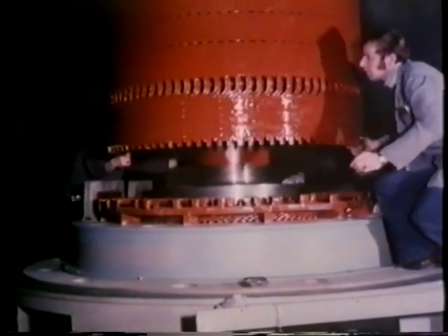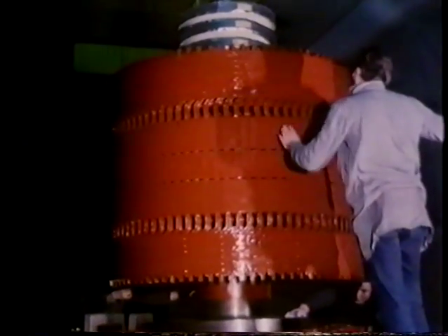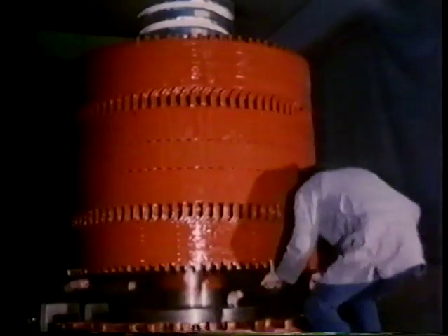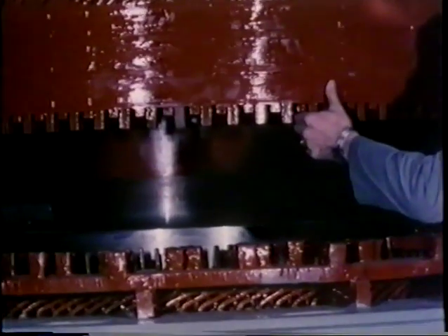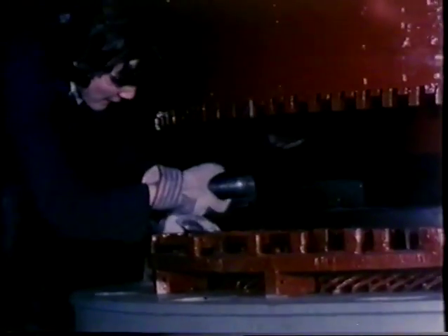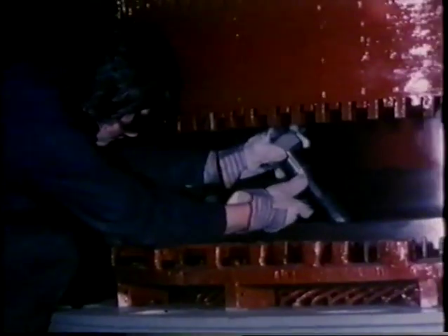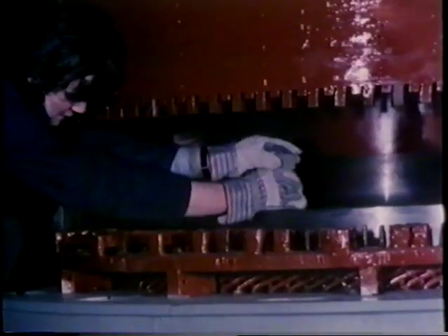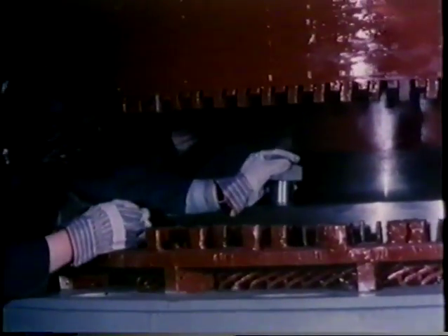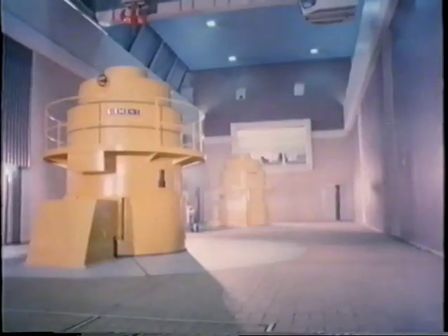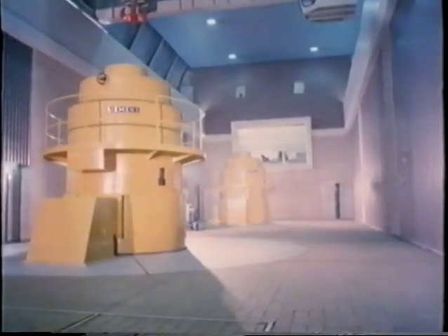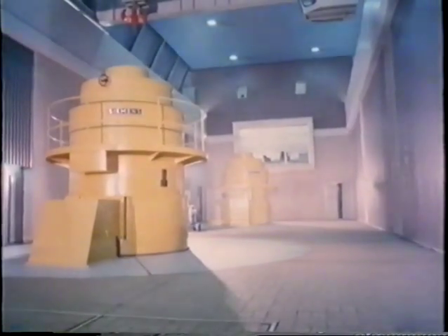A pony motor, rated 5.5 megawatts of the slip ring induction type with a maximum rotation of 592 RPM, is mounted directly on the shaft of each machine. Its speed is controlled by a liquid resistor connected in the rotor circuit. The pony motor is the only part of the unit which appears above the main operating floor level, and it is used solely for starting up in the pumping mode.